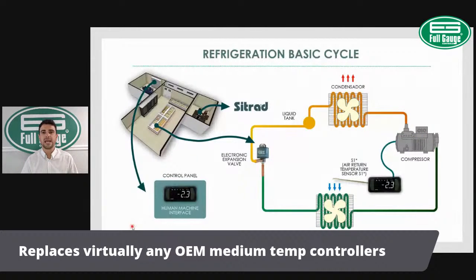So let's revisit the basic refrigeration cycle and see where the controller sits into it. So the basic refrigeration cycle comprises of compressor, condenser, expansion device, and evaporator. In a medium temp application, the controller will be either controlling the compressor or the solenoid valve. And the defrost cycle is normally an off refrigeration cycle. So that means we run the compressor for 6 hours, 8 hours, and we stop that compressor for 20 minutes to melt the ice on the coil.